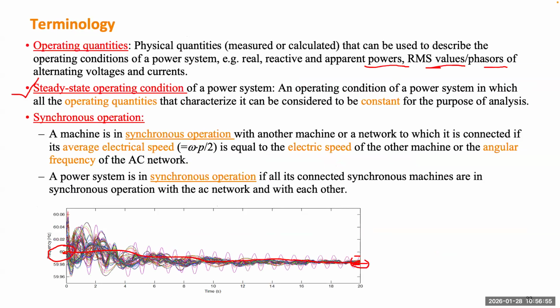Like if we use this case as one example, right? We know what the disturbance is. For example, we trip a generator. We can always use power flow to resolve it. We solve the power flow before the contingency and after the contingency. After the contingency, if we solve power flow, the power flow can still be solved. That gave you a steady state condition.